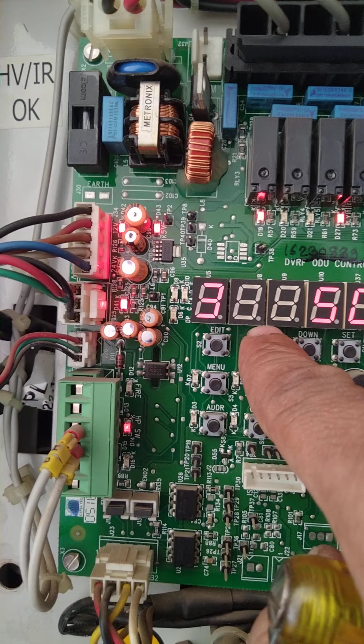It means this is a 14 ton machine, and here 6 indoor units are installed from this outdoor unit. After setting it, escape, then press the addressing button for 5 seconds. Overall this machine takes 6 to 6 - 1 outdoor and 6 indoor. From 1 outdoor, there are 6 indoor units connected to it.